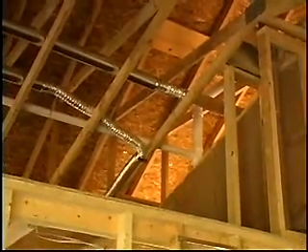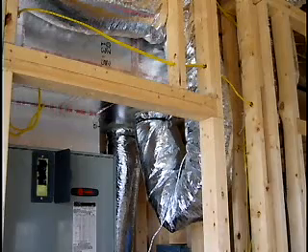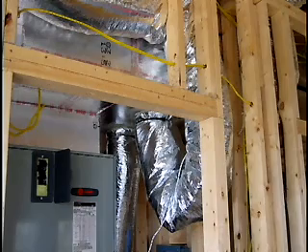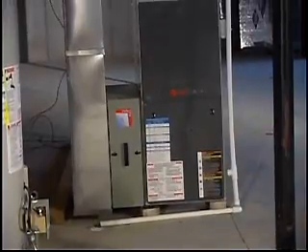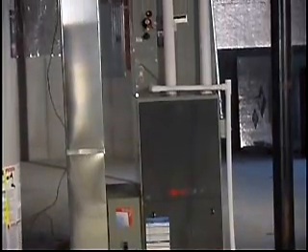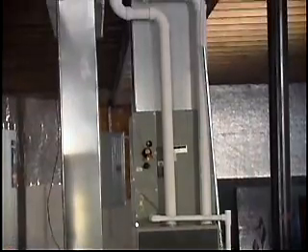Now, ductwork oftentimes is installed improperly. We have long runs that do not have long sweeping bends. We tend to crush the ductwork. We tend to fold it around corners if it's flex duct. We don't want to compress that duct so there's no way that air can flow through it. But it's really critical that HVAC systems be properly designed and installed so that the air flows through them properly and that we don't create these pressure imbalances that can cause negative or positive pressures across the building envelope, so that our system actually helps our home be more energy efficient and more comfortable to live in.